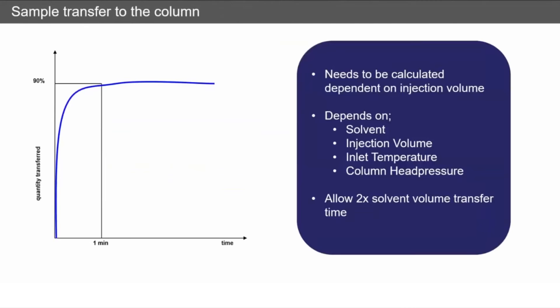We need to think about the transfer onto the column. We need to calculate this based on: what solvent we're injecting, the injection temperature, the inlet temperature, the column head pressure, and the flow going onto the column. We need this time to be roughly two times the solvent volume once it expands to allow 90 to 100 percent to pass onto the column. This is really important because if we run shorter than this we'll get irreproducible injections.